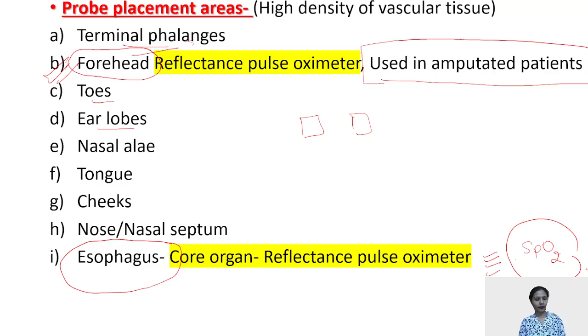See, one thing which is not very important for you all to know is that pulse oximetry can be of two types. One is the transmitted manner. Second is reflective, that is, the photodiode and the sensor are present on the same side. That is the reflectance pulse oximeter. But the importance is that in amputated patients, we use the reflectance pulse oximeter, and the area where we use it is the forehead. So when we talk about probe placements, three areas are very important: terminal phalanges, your esophagus, the core organ which can be used, and third, in amputated patients, you can use the reflectance pulse oximeter which can be applied on your forehead.